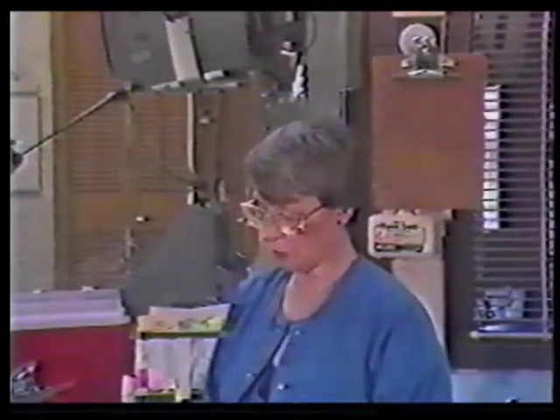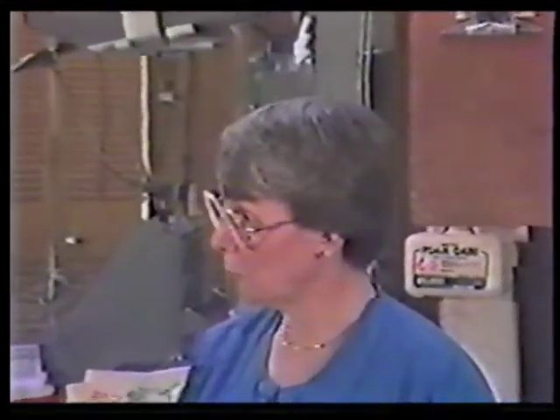So your staff is familiar with the policy for reporting faulty medical devices? Yes, we just reviewed the policy. Medical devices consist of almost anything used in patient care or diagnosis except for drugs. We talked about what to do if an incident occurs. First, attend to the patient, then fill out the faulty medical device report and remove the device from service. Then we're to keep all the packaging, materials, disposables and this kind of thing.